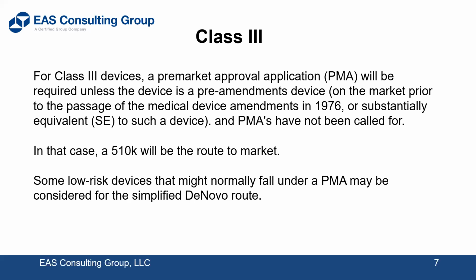And that's a subtle point. There's room for discussion and argument and disagreement between yourself and the agency on that. Of course, they have the final say. So the key point of a 510K basically is to show your product has the same safety and effectiveness issues as a predicate device on the marketplace, where the FDA can look at that predicate device, see its history, consider the types of problems it has already generated with the patient population, and view your new product against what is already out in the marketplace to see if there's any additional issues of safety and efficacy.